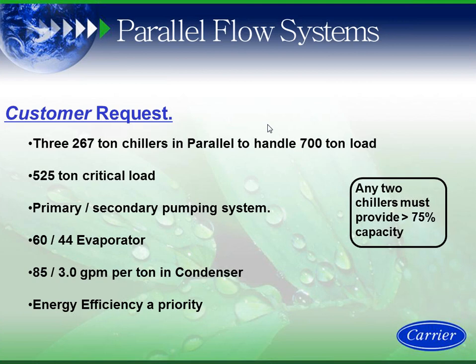So I oversized machines to have 3 267 tons to handle a 700-ton load. Because really, three 233-ton machines would actually handle a 700-ton load. I have a primary secondary pumping system. I have a 44-degree leaving water temperature and a 60-degree return, 85 entering, 3 GPM per ton, and the end user's request was energy efficiency is an absolute priority.